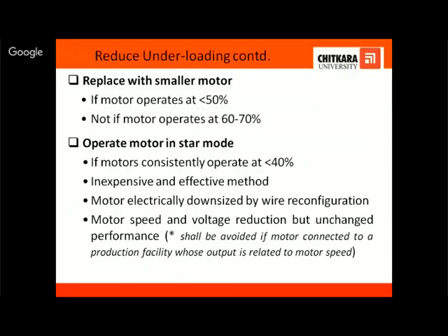You can rewire the motor; there can be a wire reconfiguration and the motor can be connected in star. This is one of the very cost effective methods, but when we do this, the speed also goes down. Now this recommendation should not be given to a production facility whose output is related to motor speed. So when we give recommendations, we need to understand the working of the motor and the working of the process. It should not happen that we have gone for the energy efficient measure, but that has affected the quality of the production.